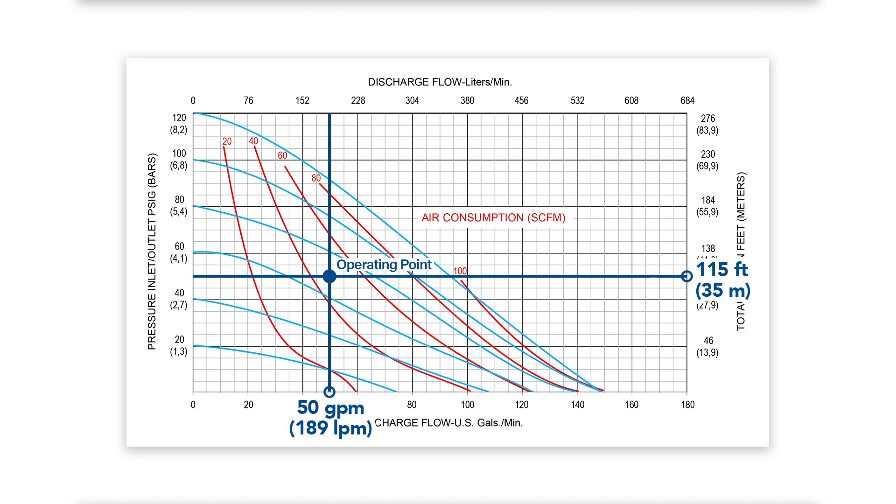In this example, the operating point is in between the 60 PSI and 80 PSI air inlet curves. Thus, the required air inlet pressure to operate the pump would be 70 PSI.